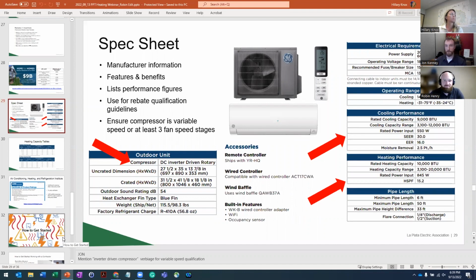We'll take a look at what that looks like in the real world. The other thing you'll see is we require two stages or variable speed. If you can't find that terminology on your spec sheet, as soon as you see DC or inverter driven, that's variable speed - it'll qualify from that. Almost all highly rated systems now have variable speed motors; that's really how they're achieving efficiencies like this.